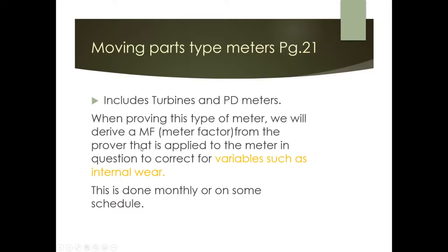When proving moving-parts meters, we derive a meter factor from the prover and apply it to the meter in question. The purpose is to correct for variables such as internal wear, dimensional changes, and leakage. The meter is verified against something more accurate, the error is determined, and a meter factor is applied. This is typically done monthly, semi-annually, or annually on a schedule.